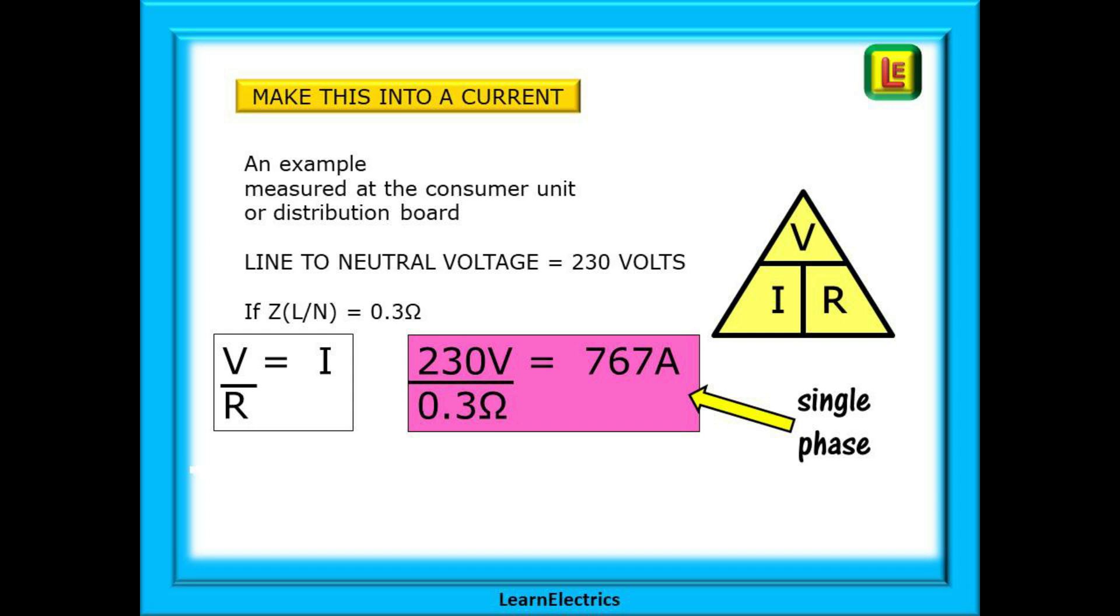Now let's make this into a current. We can measure the prospective short circuit current at the distribution board. The line to neutral voltage is 230 volts and let's say that the loop resistance is 0.3 ohms. Using ohms law, voltage divided by resistance will give us current. So 230 volts divided by 0.3 ohms comes to 767 amps or thereabouts. This would be a single phase fault current, the PSCC.